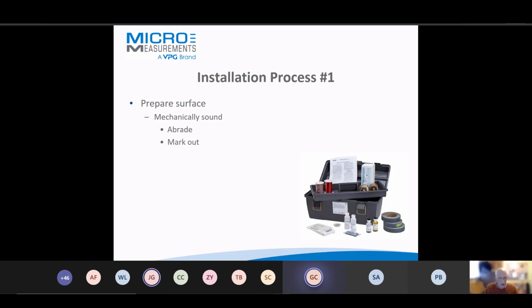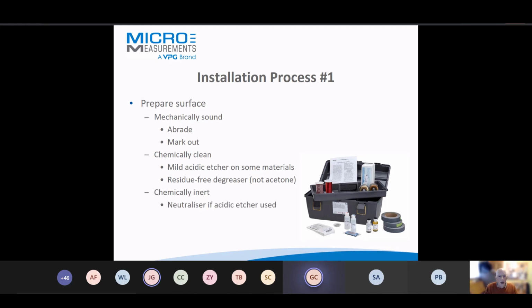So we're going to abrade back to base metal. We're going to provide some sort of marking out so we know exactly what position to put the gauge. We're going to follow that with some chemical cleaning. Some materials use an acidic etcher, very mild phosphoric acid. Perhaps use some sort of degreaser, avoid acetone or degreasers that leave a residue. And then we make sure that we reach neutral pH on the surface as well. So if you use an acidic conditioner, you must use a neutralizer for optimum pH for letting the adhesive bond to the surface.